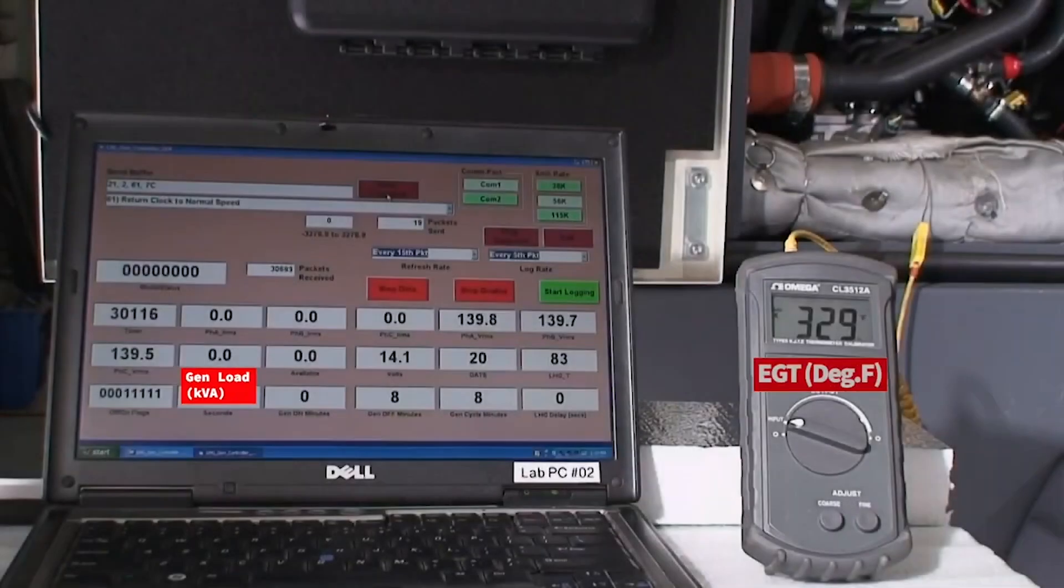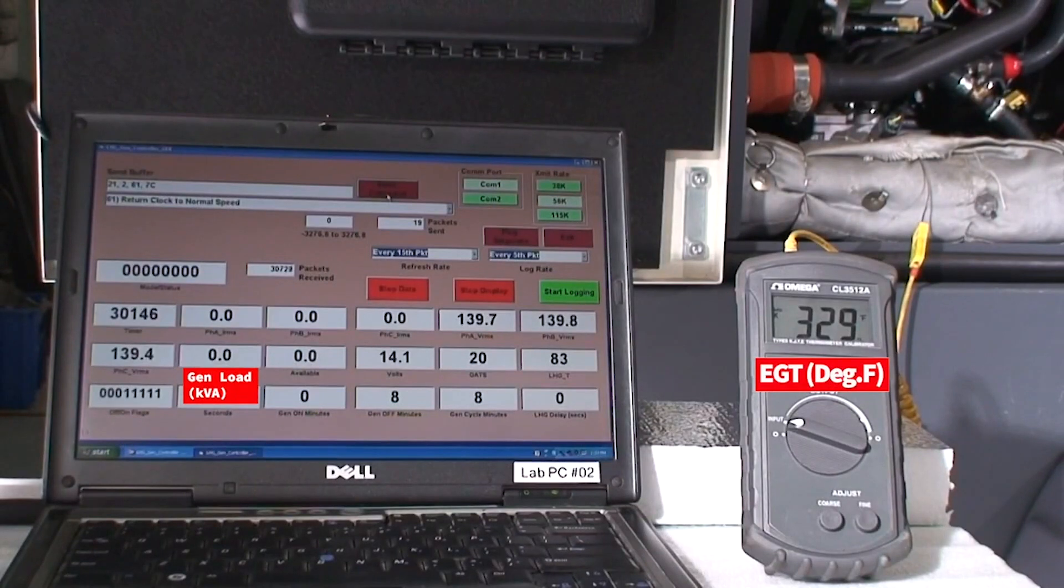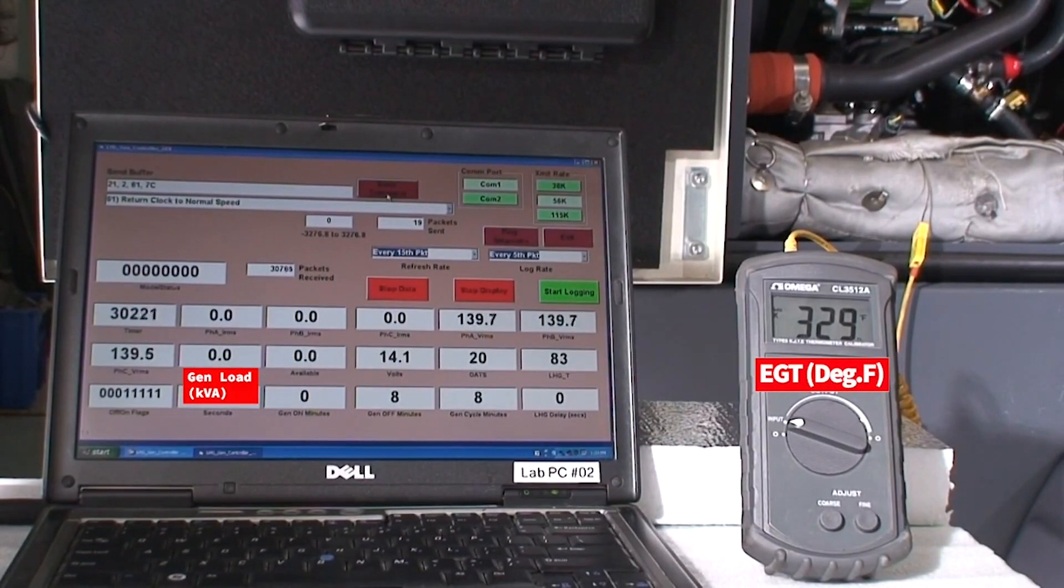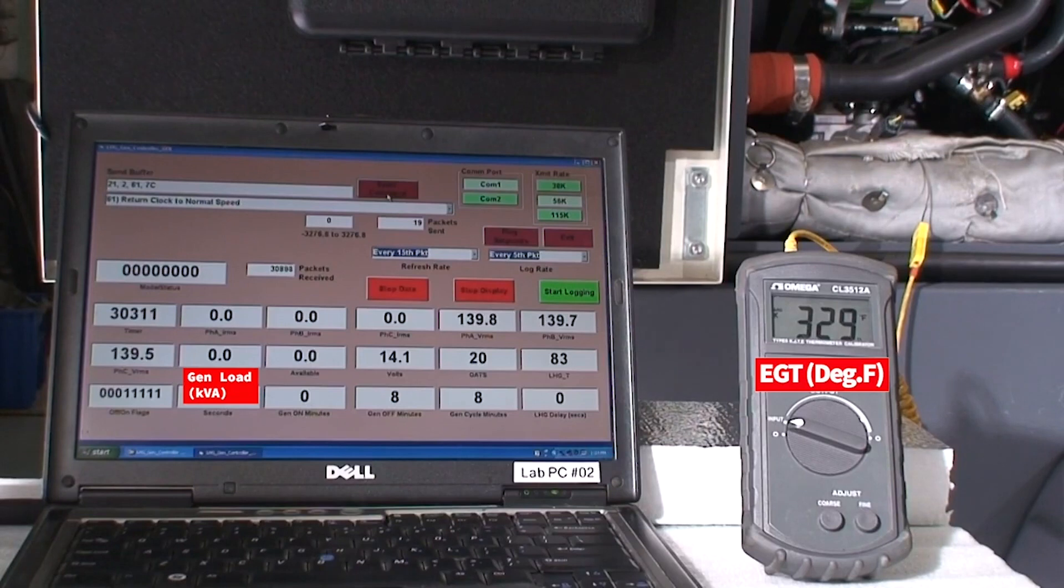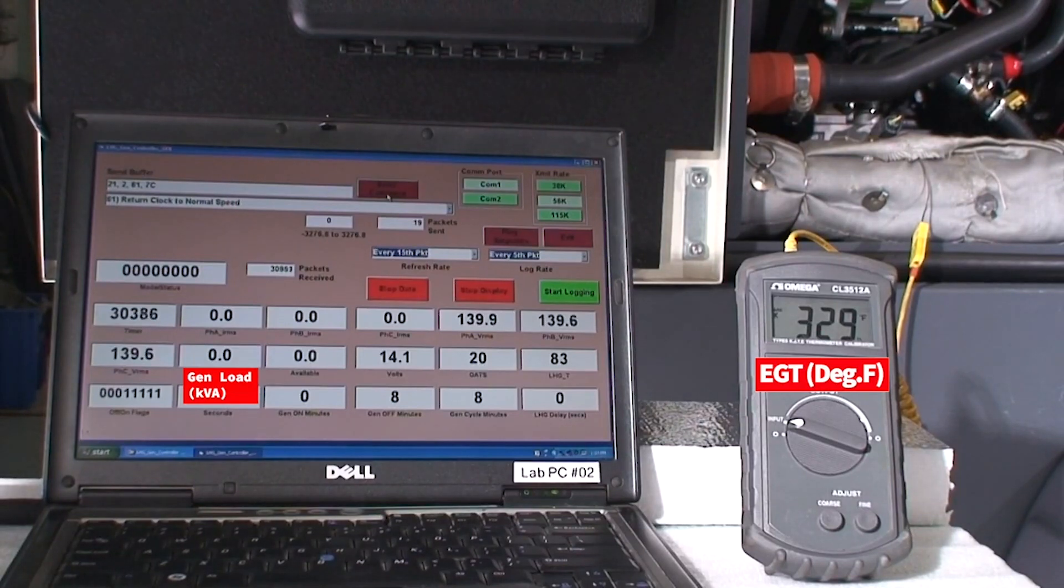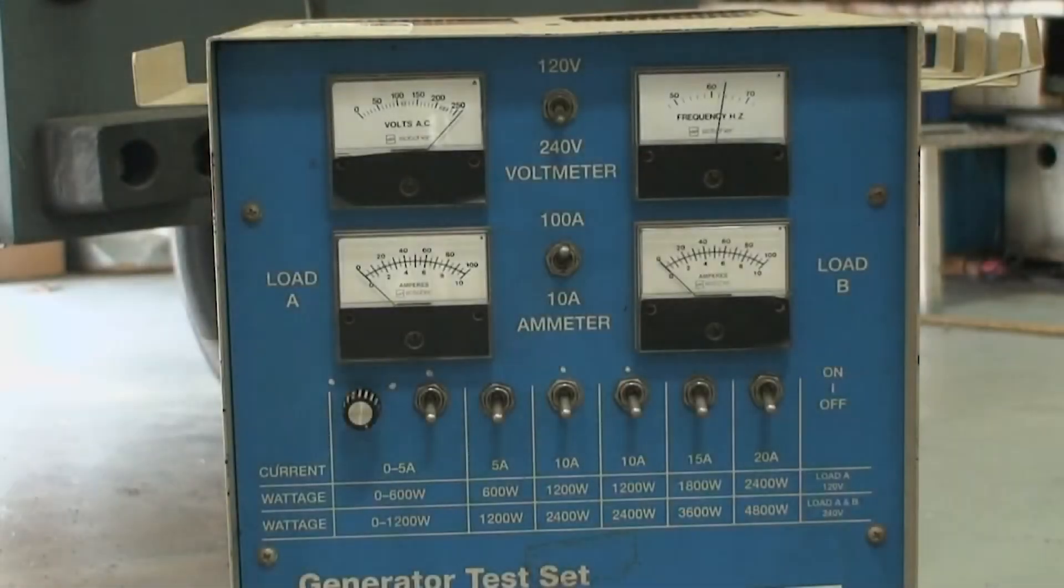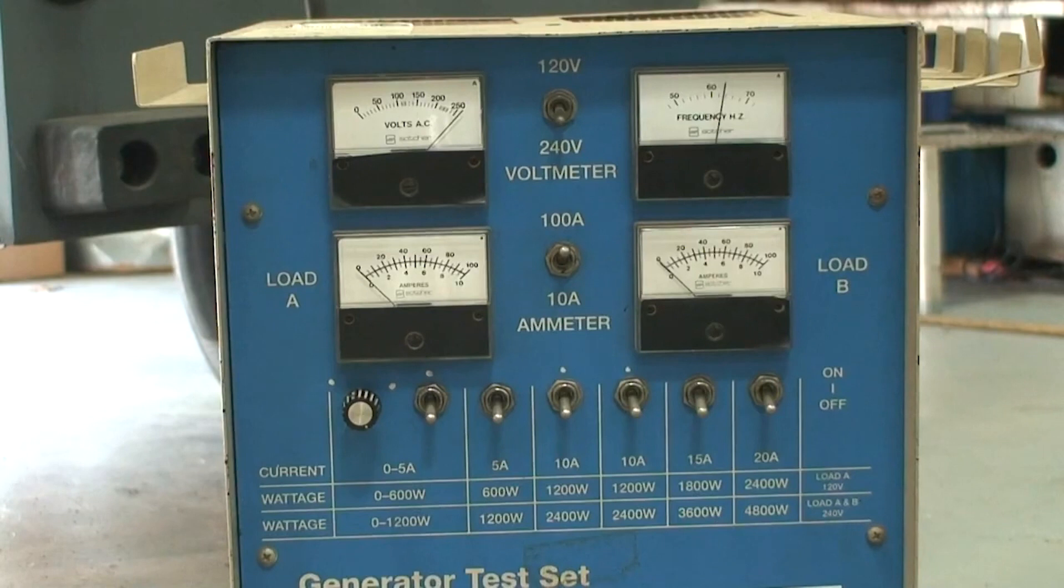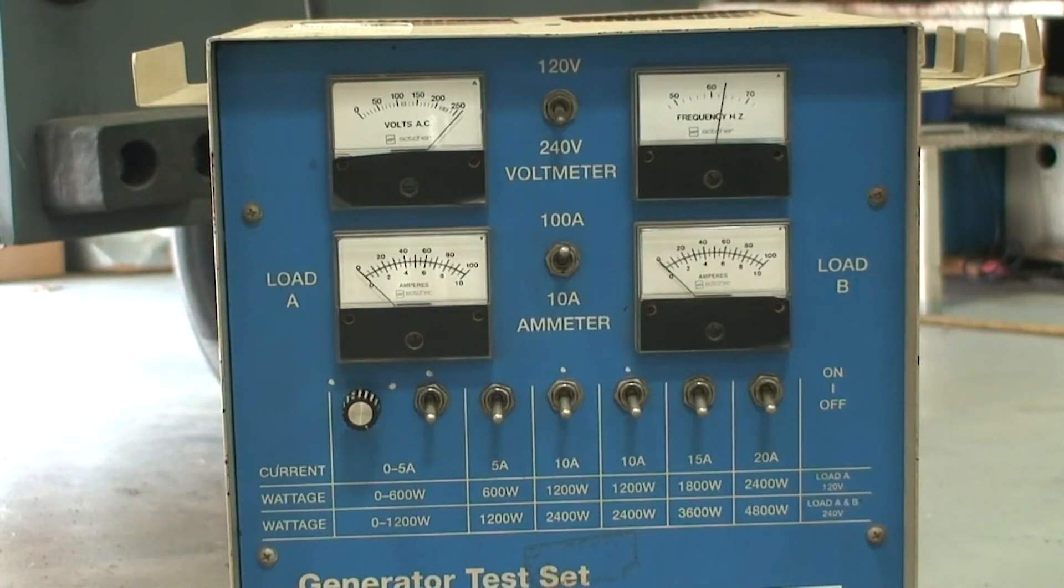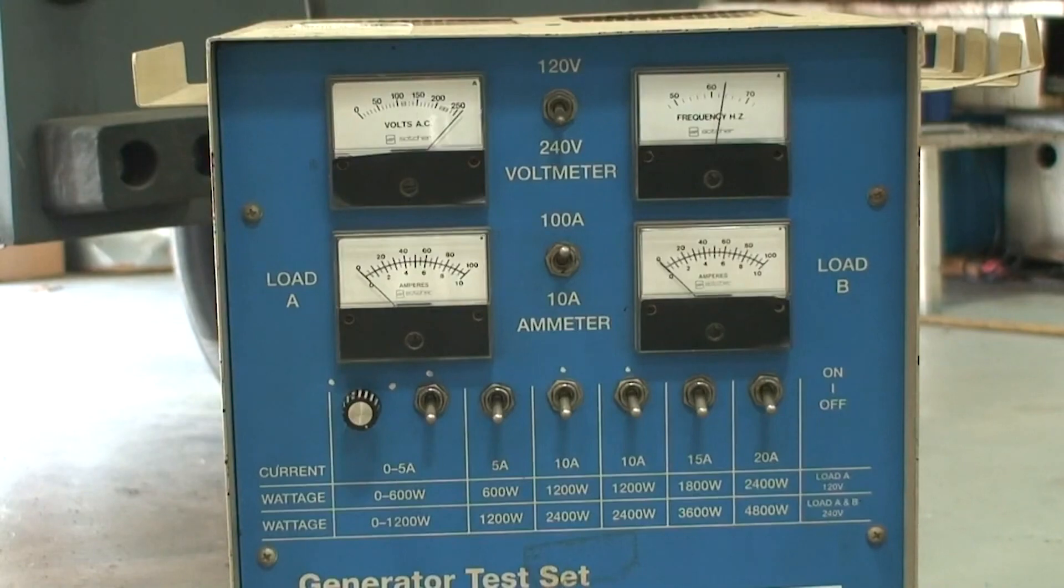We have a PC plugged into our equipment for diagnostic and configuration purposes. We're also measuring the exhaust gas temperature and we have a load bank plugged in so that we can demonstrate the effects of adding and removing electrical load to the generator.